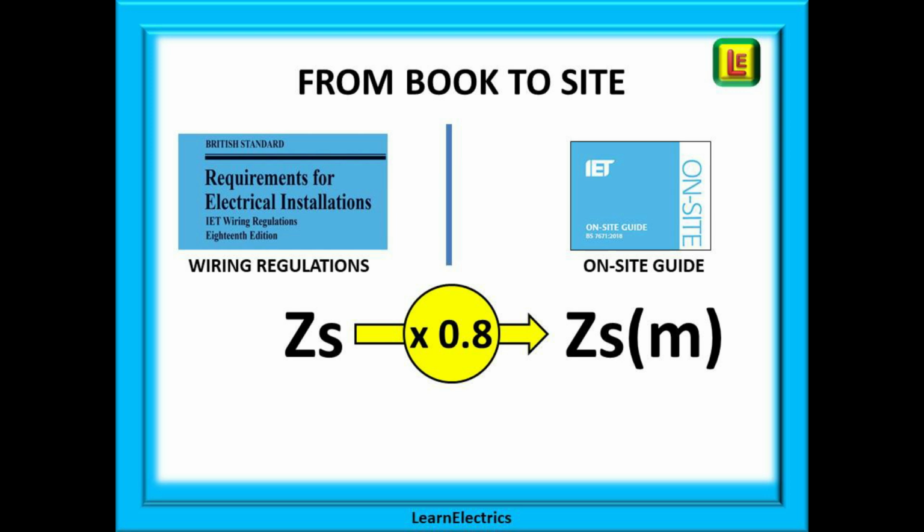If you don't have the on-site guide with you, take the ZS figures from the wiring regulations tables, multiply by 0.8 to allow for temperature rises on site, and we have ZSM. Happy days and good luck.